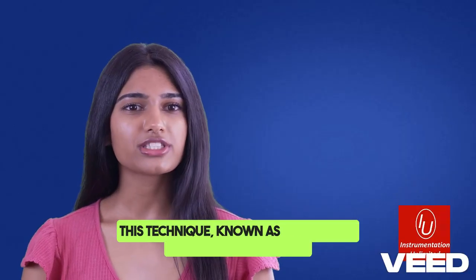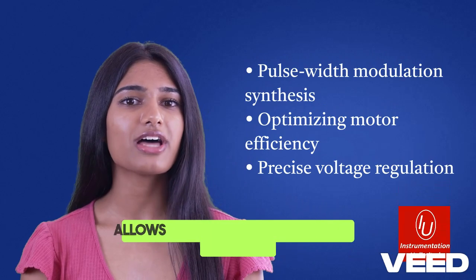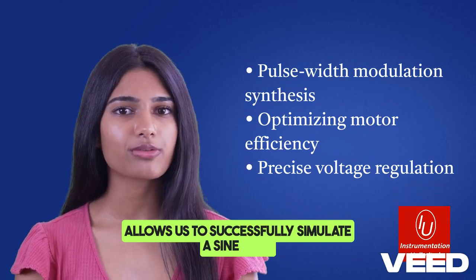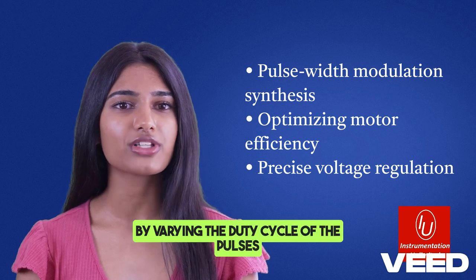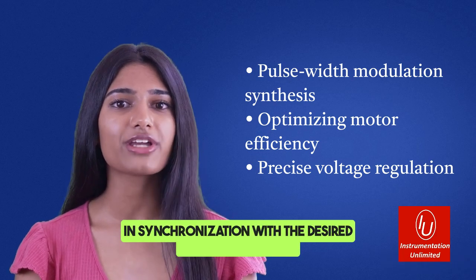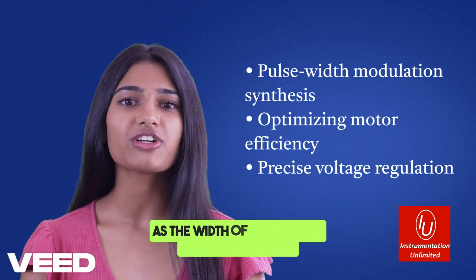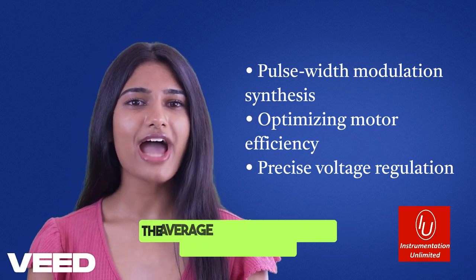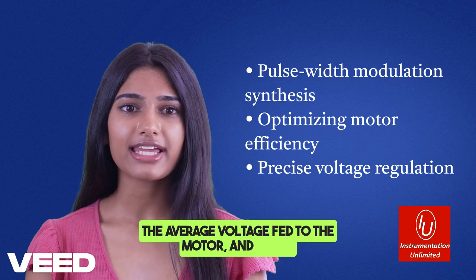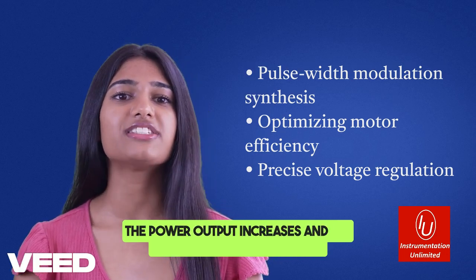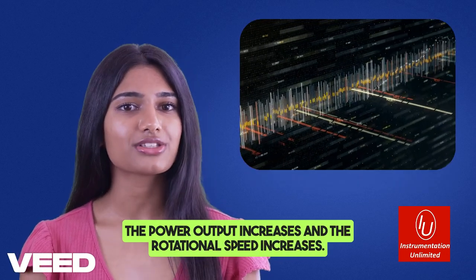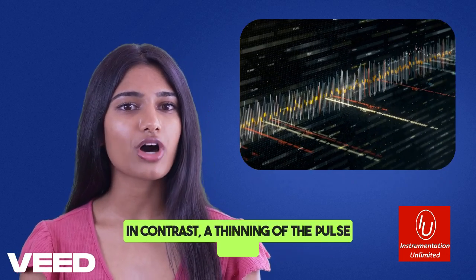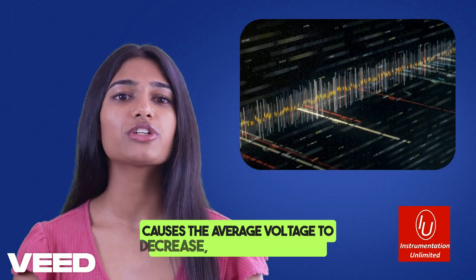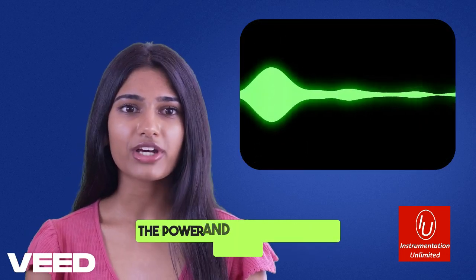This technique, known as pulse width modulation synthesis, allows us to successfully simulate a sine wave by varying the duty cycle of the pulses in synchronization with the desired output frequency. As the width of every pulse increases, so does the average voltage fed to the motor, and hence the power output and the rotational speed increase.